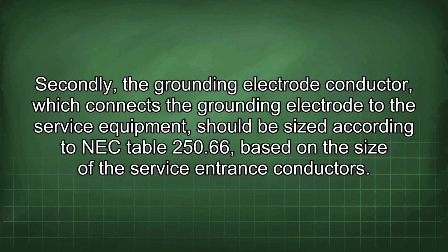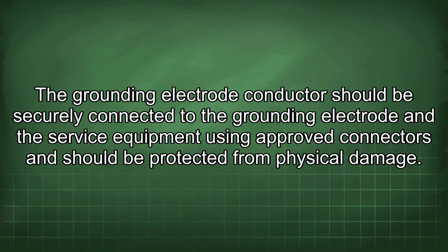Secondly, the grounding electrode conductor, which connects the grounding electrode to the service equipment, should be sized according to NEC table 250.66, based on the size of the service entrance conductors. The grounding electrode conductor should be securely connected to the grounding electrode and the service equipment using approved connectors and should be protected from physical damage.